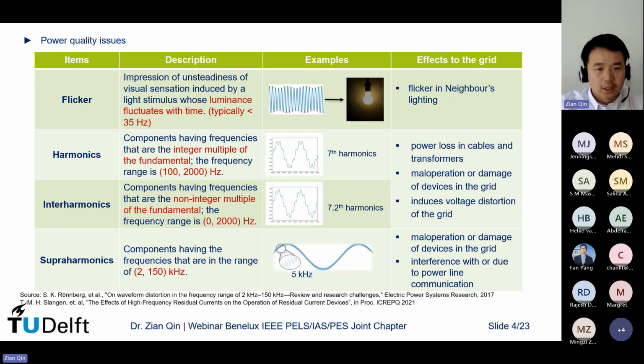The last but not least is supraharmonics. In the past, people didn't pay attention to this, but recently, because many power electronics are connected to the grid, people notice that there is also a component between 2 kilohertz and 150 kilohertz that is creating problems. They gave this a name: supraharmonics. The harm it can do to the utility grid includes, again, maloperation or damage of devices in the grid.